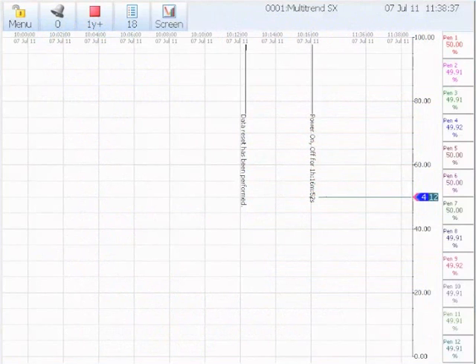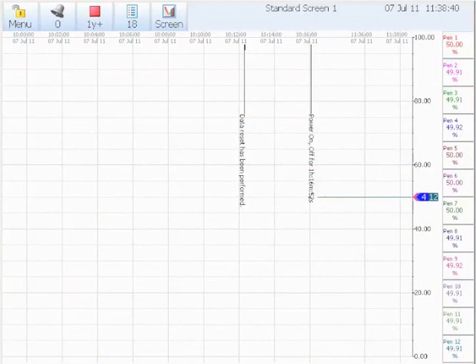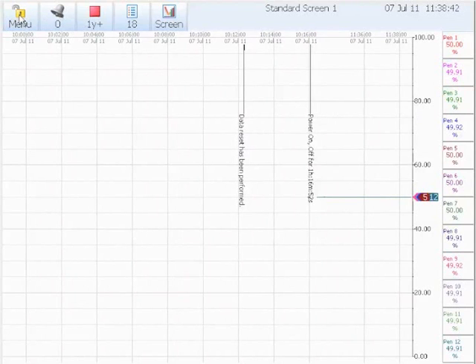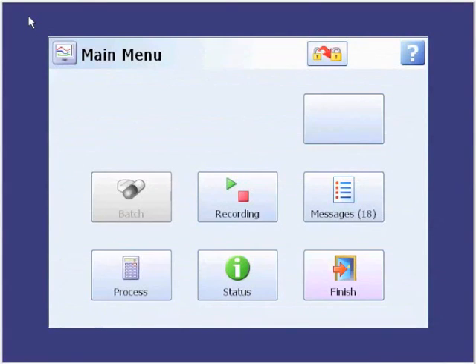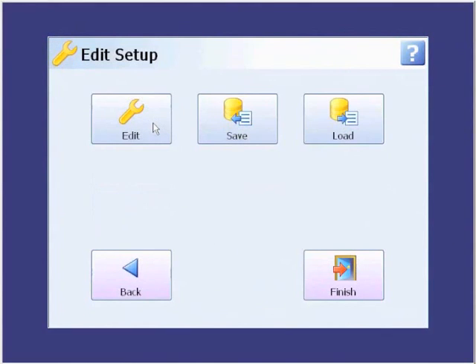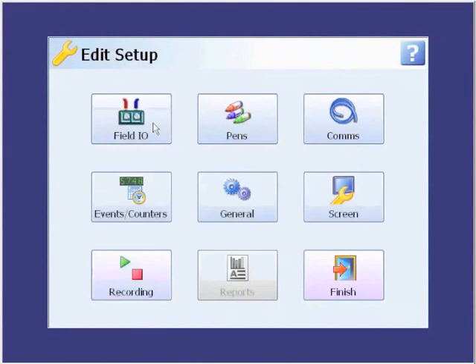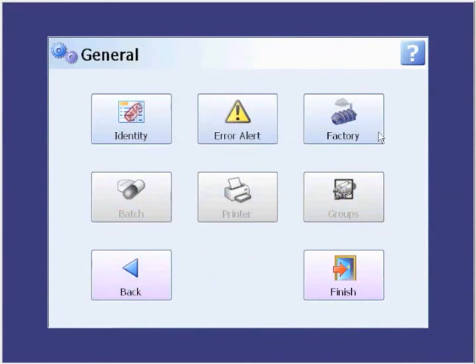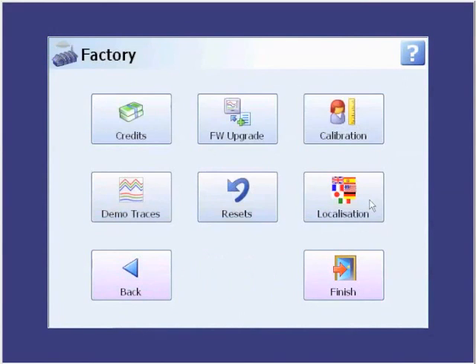When we turn the recorder on, we see that we get a trend screen. We want to navigate to the localization group, so we come in and click on the menu button. I've already logged in, as you can see from the red arrow up here, but if you don't have passwords enabled, you won't have to do that. We get to localization through Configure, Setup, Edit, General, Factory, Localization.